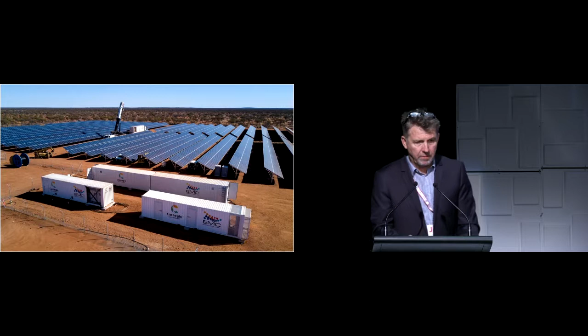This island installation is a Chevron Island. They decommissioned their refinery on that island as part of the Wheatstone project and left the island without any energy, so we were asked to build a standalone power system there, which we've done. It's been operating for 21,942 hours, with the diesel generator runtime less than 1,000 hours. So, regarding penetration that people were talking about yesterday, this is a 98% solar powered island, 2.5 years operating, no outages.